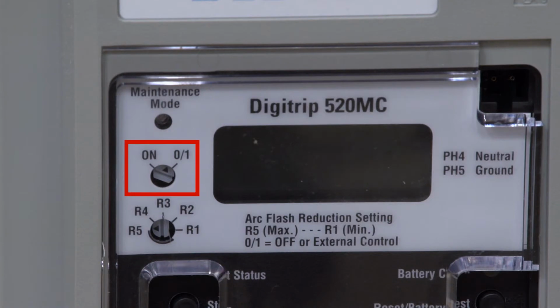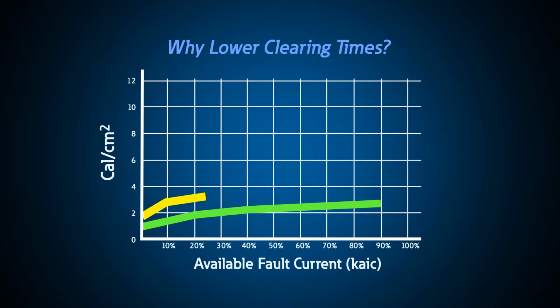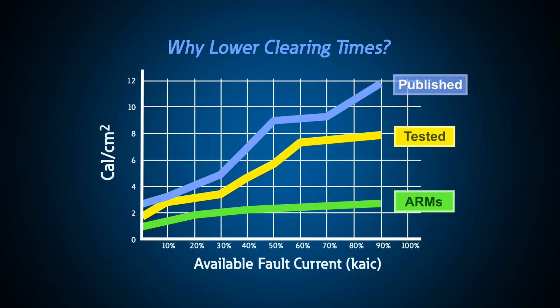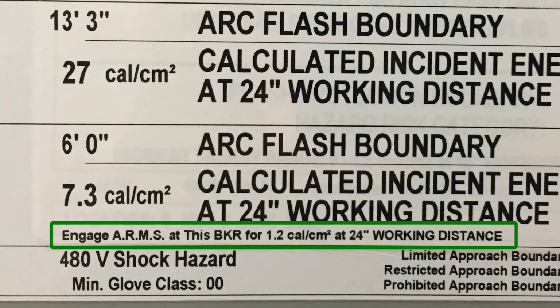For example, to reduce the fault clearing time, the arc flash reduction maintenance system allows you to use 2 settings on a circuit breaker. One for normal coordination, one that is faster than instantaneous setting on the breaker. This second setting, when activated during a maintenance operation, bypasses the microprocessor to clear the fault even faster than a ZSI or instantaneous trip time. These lockable switches should be part of every lockout-tagout procedure. In this case, the arc flash energy is reduced from more than 20 calories to less than 1.2 calories during maintenance operations when faults are more likely to occur.